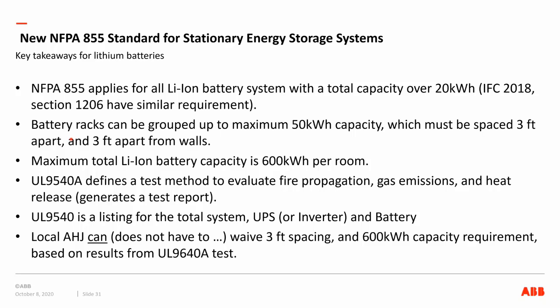That's a total. So for a large data center that will support 4 to 5 megawatts of UPS, with a 1 megawatt UPS we would typically need 4 or 5 cabinets, and they would have to be spaced apart if complying to 855 without anything else.